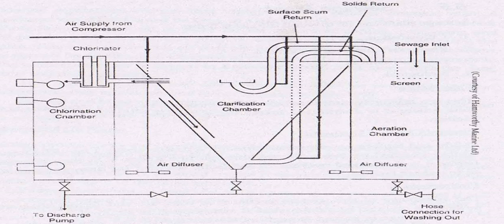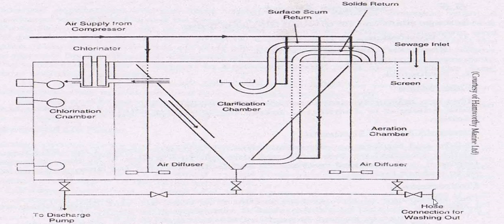If we need to pump out these tanks separately — for example the aeration tank — we use these valves and hose connections. We need to prime the discharge pump first: close all three valves, open this valve, connect the water line to this hose and prime the pump, then close this valve, open this valve, and start pumping out the aeration chamber.